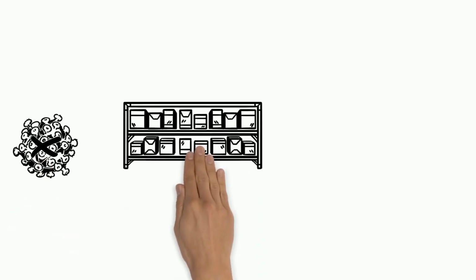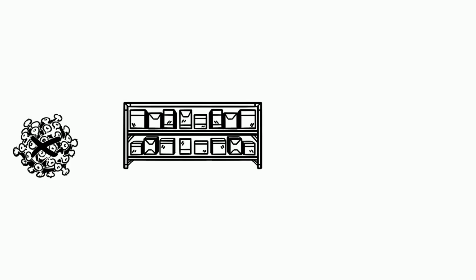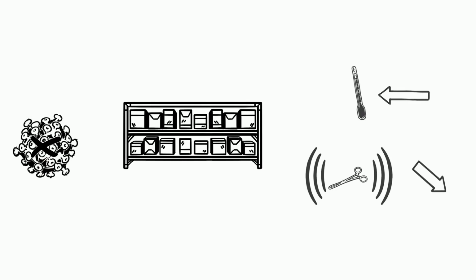The preservation of sterility must always be defined by the user. This is significantly influenced by so-called events or changes. Constant ambient temperatures and reduction of movements are the key to long and safe storage. The proper reprocessing of medical devices also includes the documentation of all reprocessing steps. These must be fully documented for each medical device.